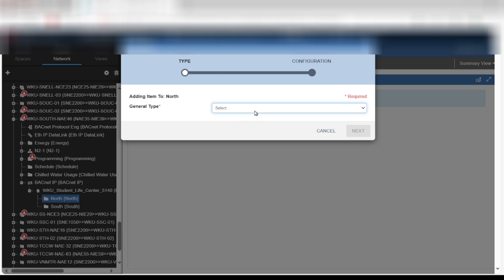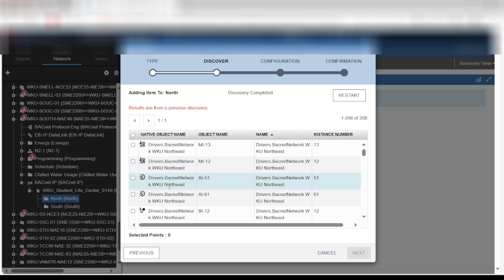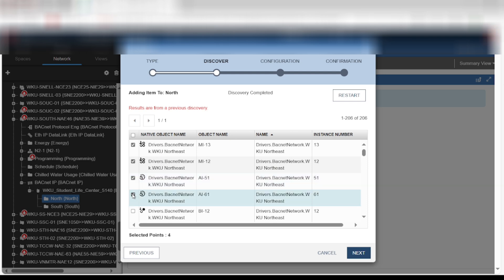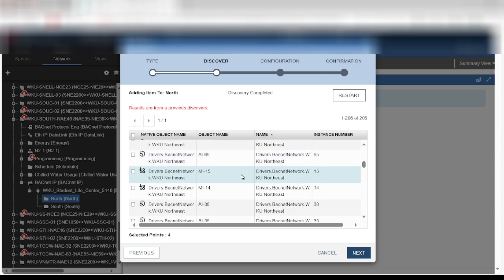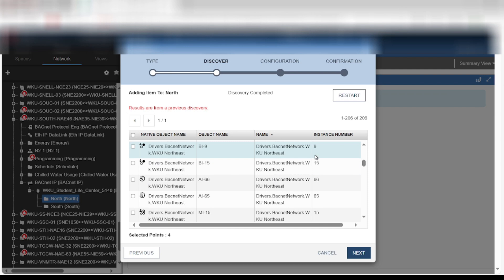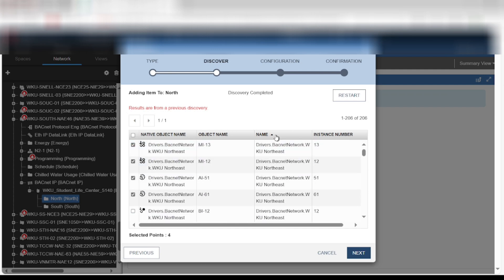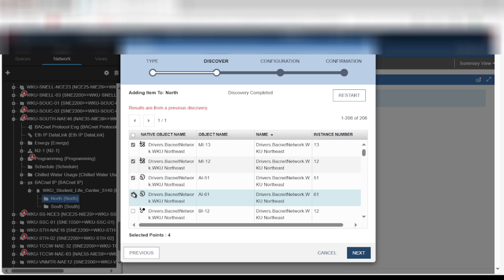You can see we have a couple of folders created underneath the Jace after it's pulled into our system. I'm simply going to click into one of those folders — currently no points — and when I hit the plus sign it gives me the option to pull in those points. I hit discover, let it go through the process of discovering all the points in the Jace, and then I simply go through and select the individual points I want, breaking them up by side into the appropriate folder.